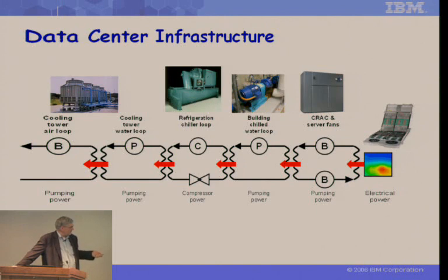These are all the things that take place: here's the computer room air conditioner with the blowers, then it ties into the building chilled water with pumps, then into the refrigeration loop with compressors, then into the cooling tower with pumps that pump that water, and then into the big blowers that exhaust the heat load back out to the environment. All this basically to cool that handful of chips down to 85°C.